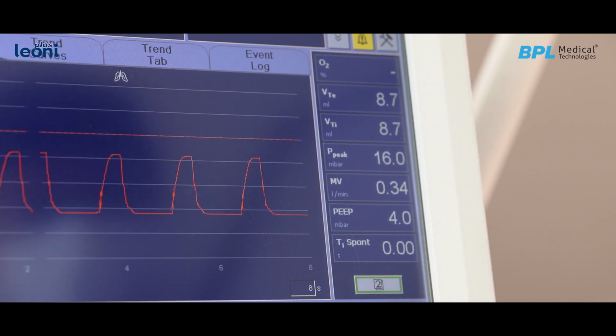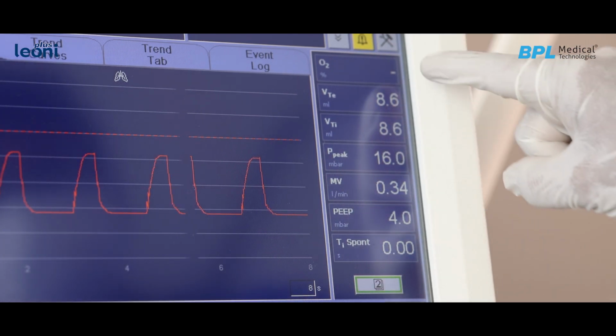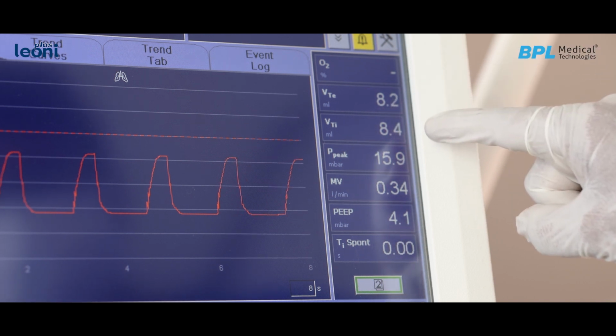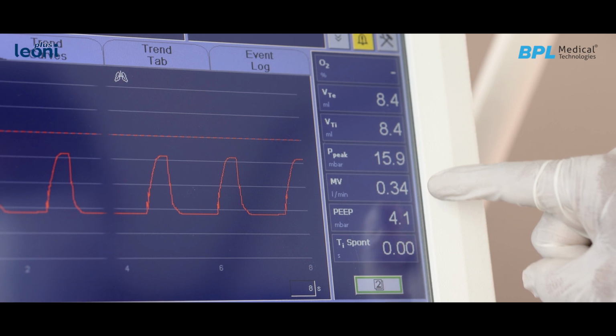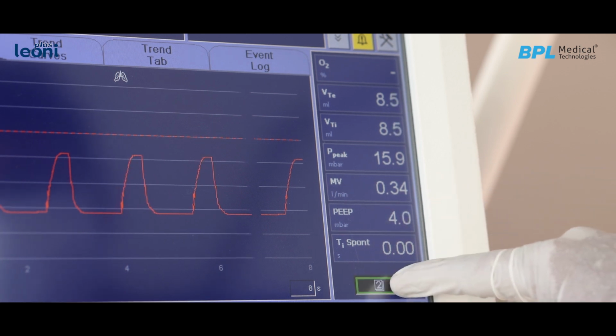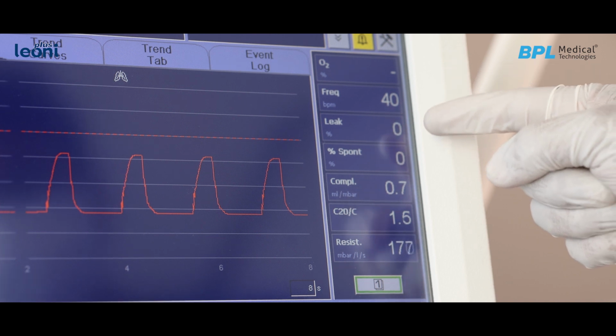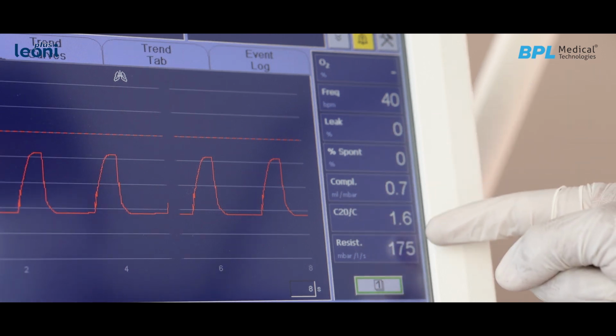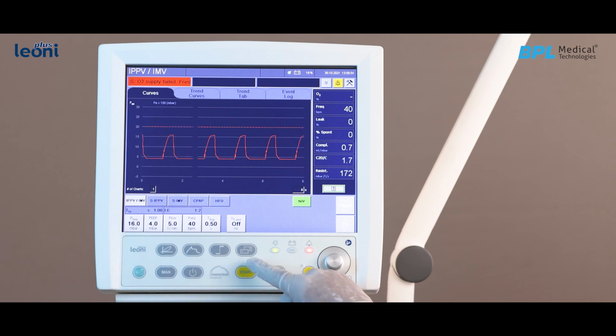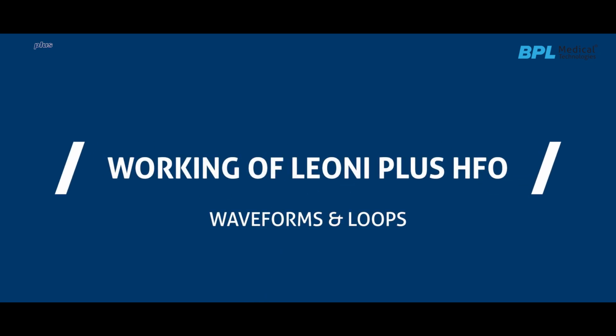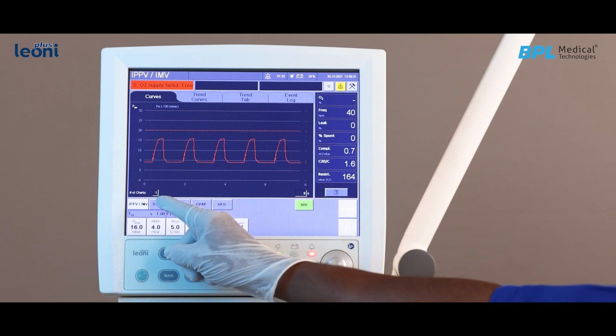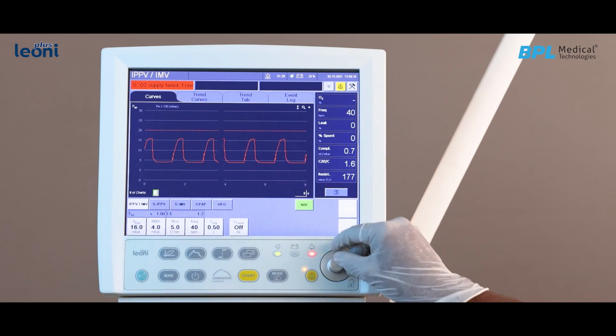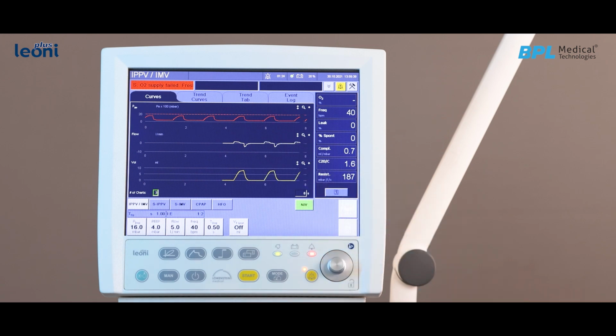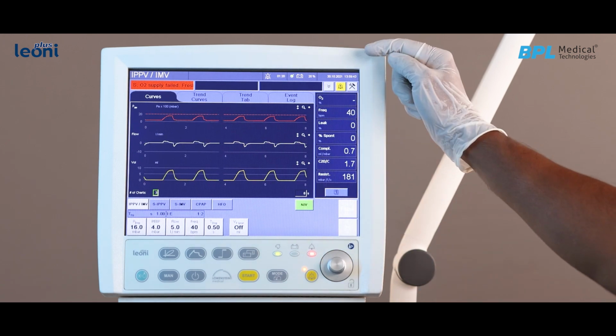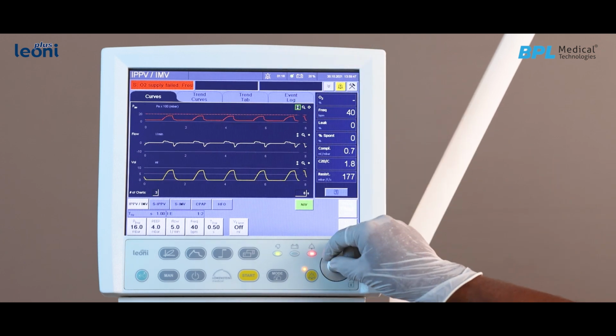The main screen will continuously monitor important parameters such as FiO2, expiratory tidal volume, inspiratory tidal volume, peak airway pressure, minute volume, PEEP, I/E ratio and frequency, leakage, compliance, C20/C index, resistance. More parameters like loops, alarm auto set can be seen by touching the keypad. Leoni Plus HFO can display up to 3 waveforms simultaneously in different colors. Waveforms are user configurable, where users can manually scale, zoom, and choose to view 3 loops with an option of saving one reference loop.